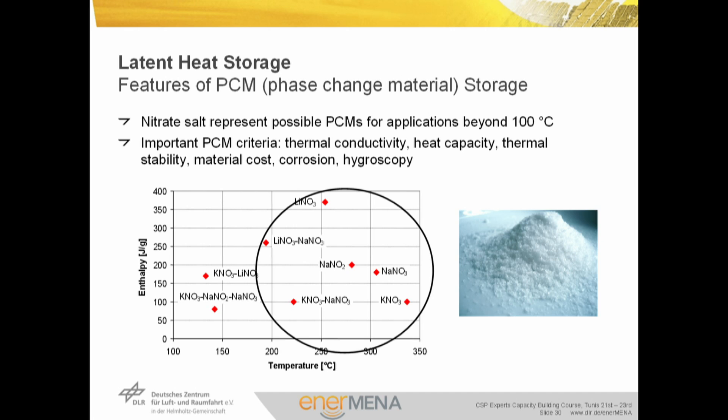Constant temperature energy storage can be implemented using latent heat storage material, where the energy associated with the phase change of the storage material is used for energy storage. Candidate materials for the temperature range exceeding 100°C are nitrate salts. Important criteria for the selection of phase change materials (PCM) include thermal conductivity, heat capacity, thermal stability, material costs, corrosion, and hygroscopy.